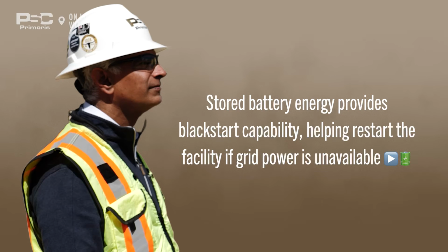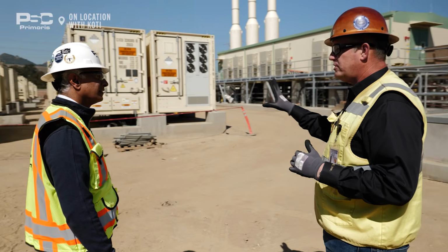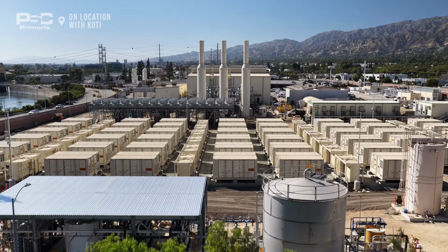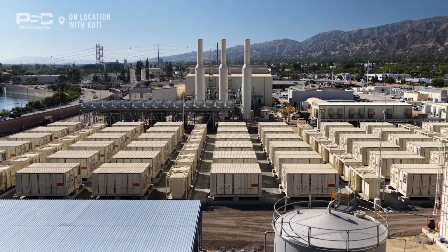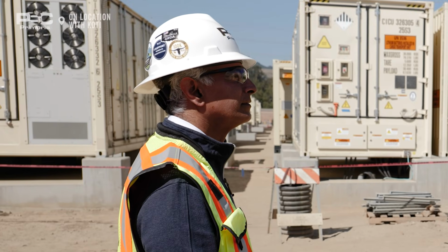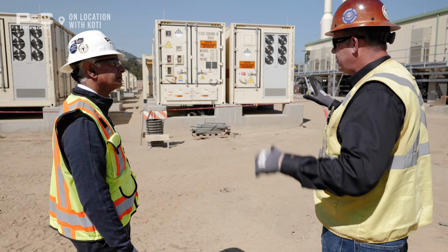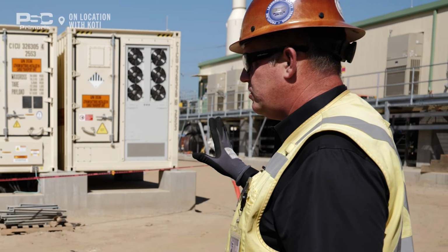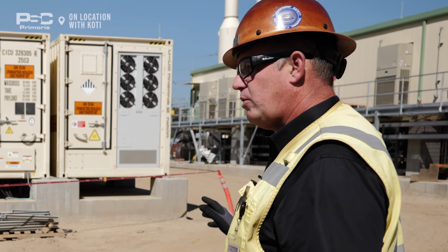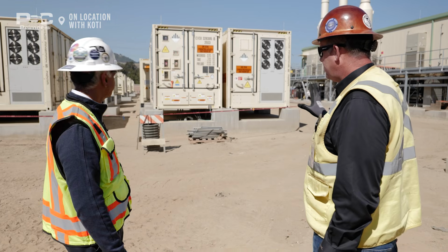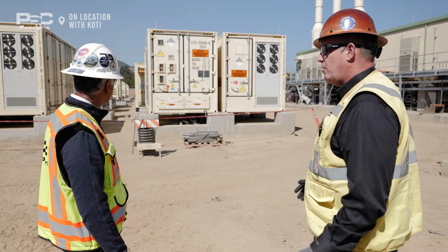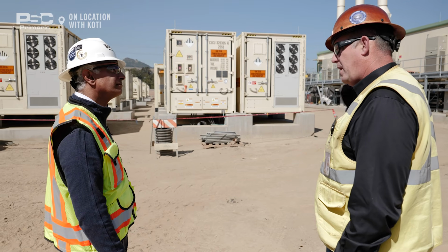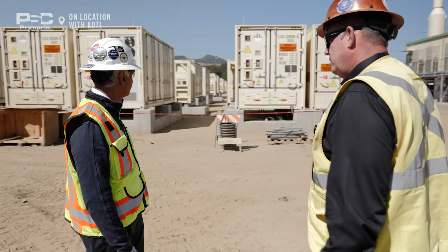Of our first two blocks, our batteries are going to have a minimum SOC level, can't go below 30%. That'll provide us black start for this entire project. It's super important since we are not connected to Cal ISO in this area. They're their own little load block, so they have to soft start, be able to black start if there's any emergency, fires or earthquakes or anything of that nature. It'll help get them online with the city and help provide power either to here or help out with Burbank or LADWP.